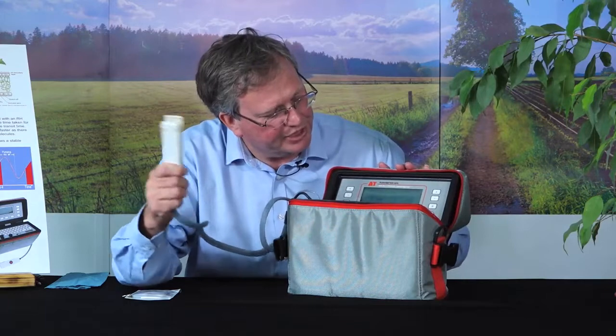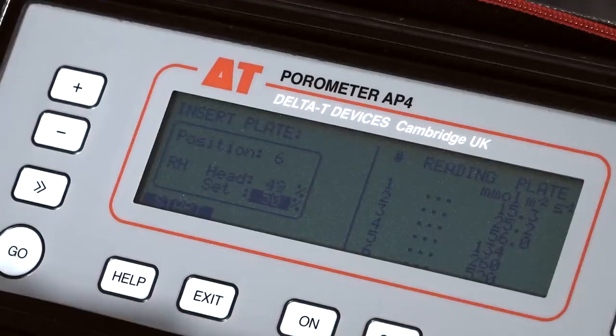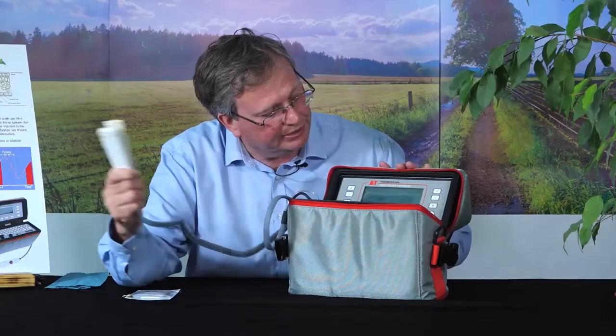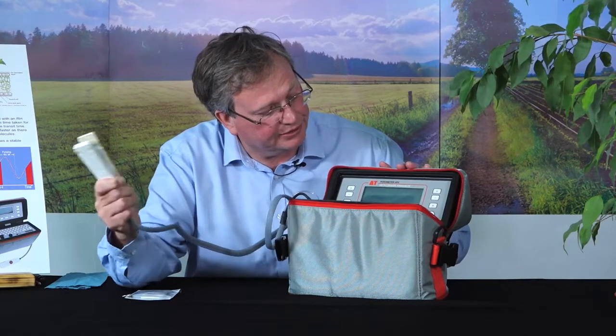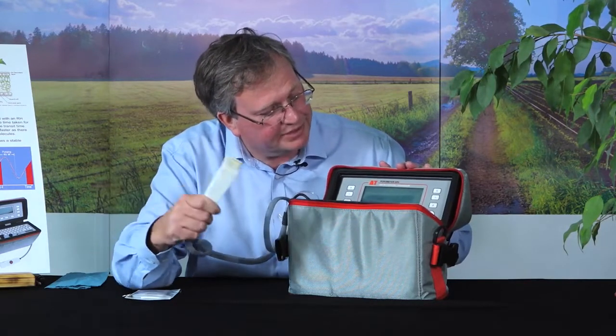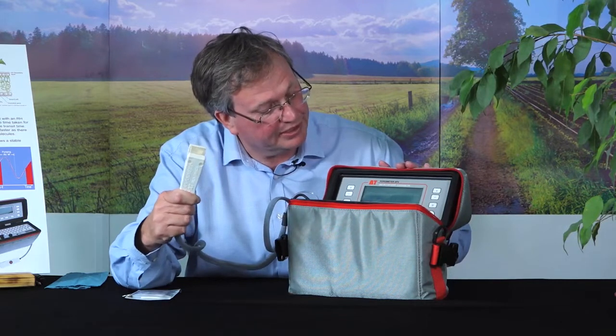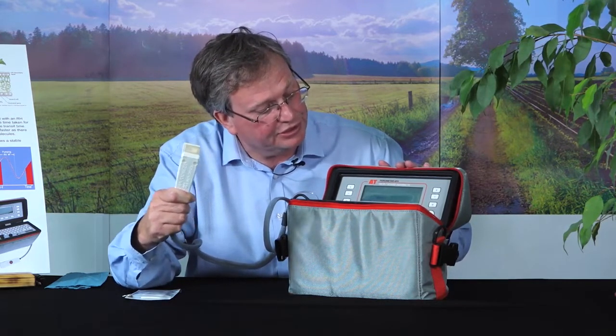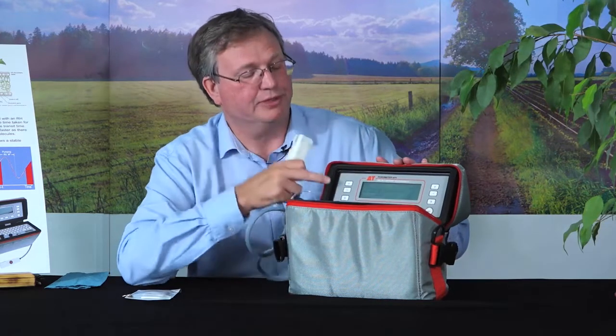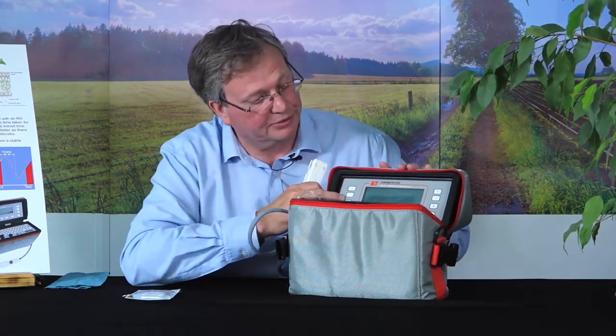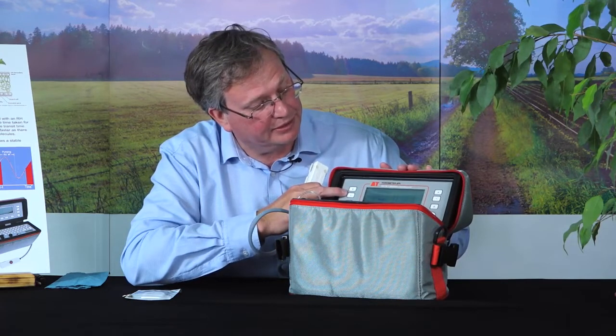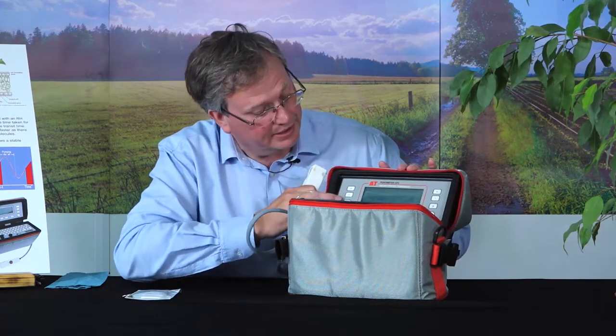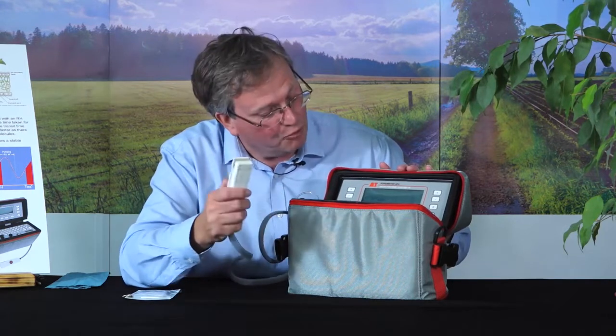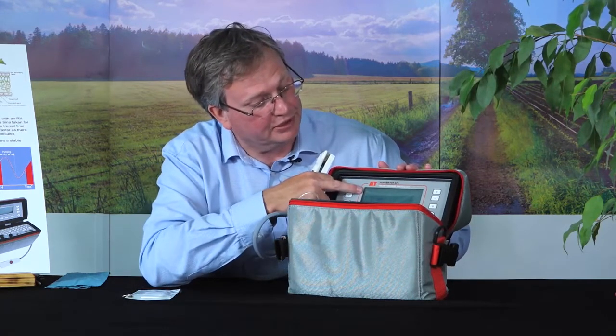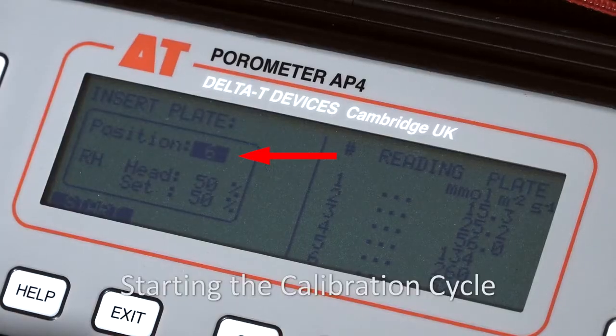And you can see the value changing on the screen. If you blow across the head, the values change. So we just want to make sure that the value we're seeing here is what the plant is experiencing. So once we think we've got a stable value for the head measurement, we can adjust the set point to just below that value. And we can move this set point plus or minus 5% increments. So we want to be just below the value for the head and then accept that. Once we do that, we can start on position 6 of the calibration plate.